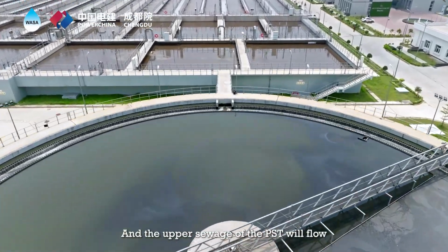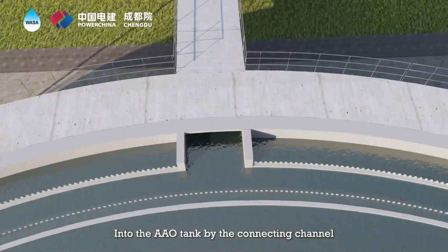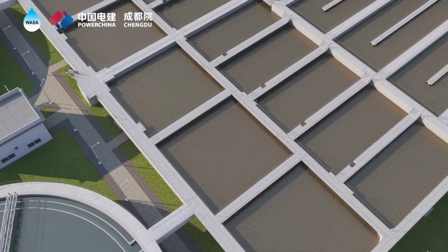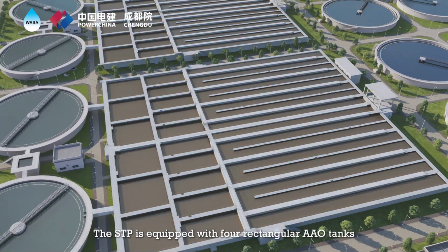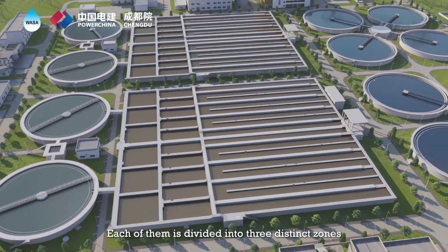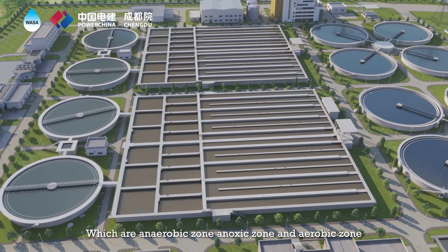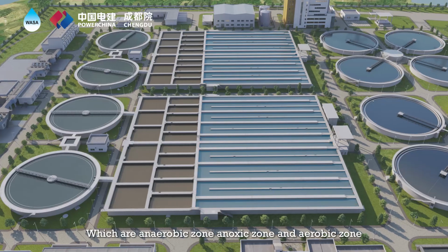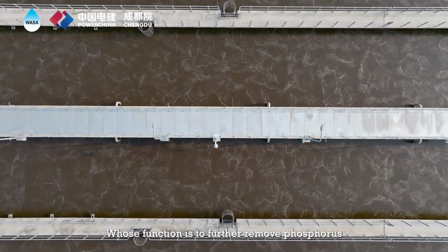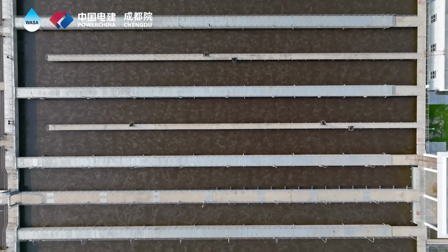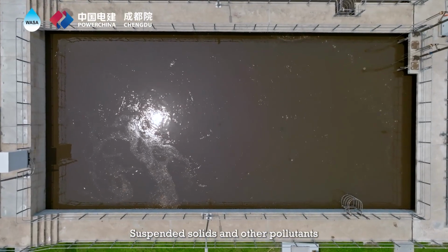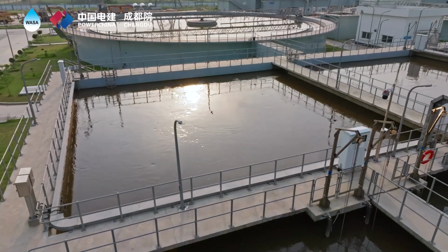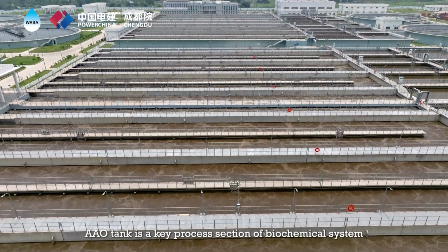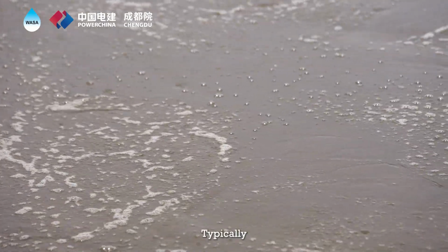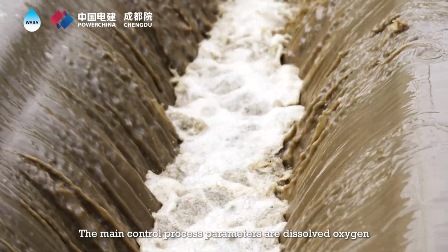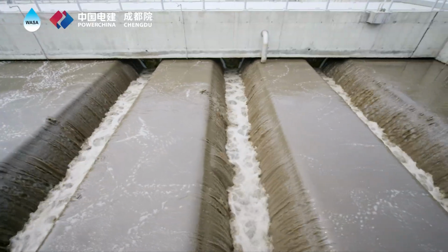The upper sewage of the PST will flow into the AAO tank by the connecting channel. The STP is equipped with 4 rectangular AAO tanks. Each of them is divided into 3 distinct zones, which are anaerobic zone, anoxic zone, and aerobic zone, whose function is to further remove phosphorus, BOD, ammonia nitrogen, suspended solids, and other pollutants in sewage by activated sludge. AAO tank is a key process section of the biochemical system. Typically, the main control process parameters are dissolved oxygen and mixed liquor suspended solids.